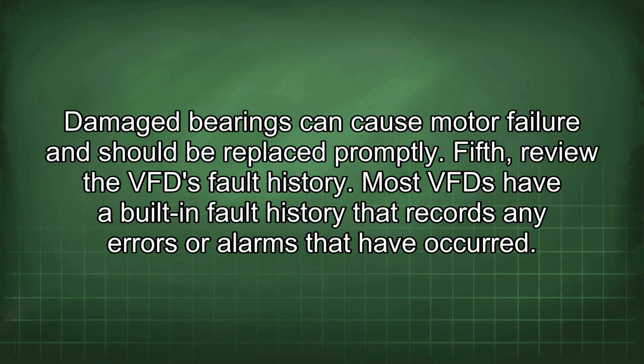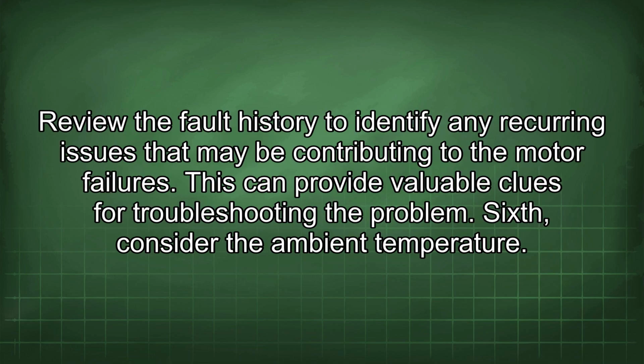Fifth, review the VFD fault history. Most VFD have a built-in fault history that records any errors or alarms that have occurred. Review the fault history to identify any recurring issues that may be contributing to the motor failures. This can provide valuable clues for troubleshooting the problem.